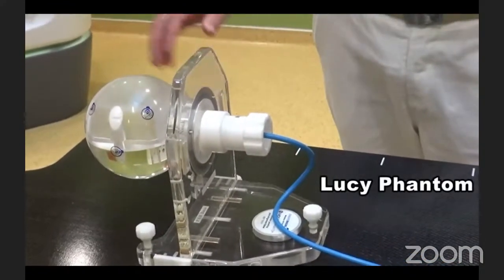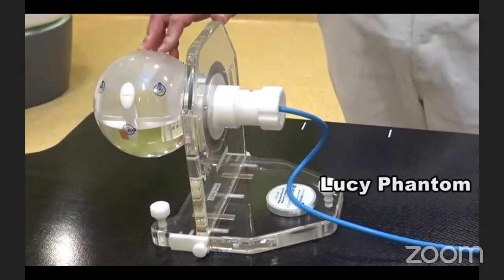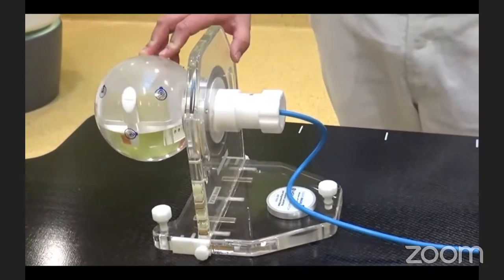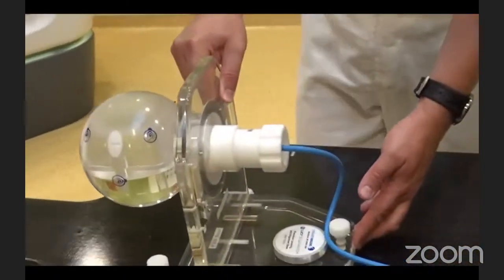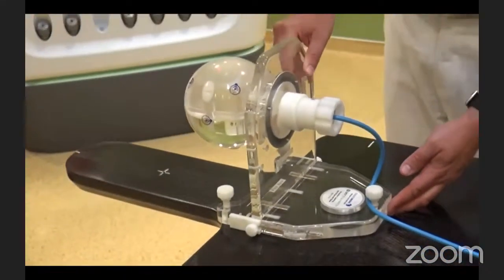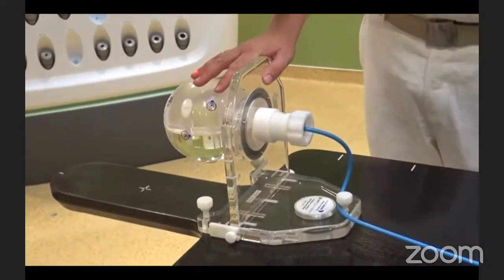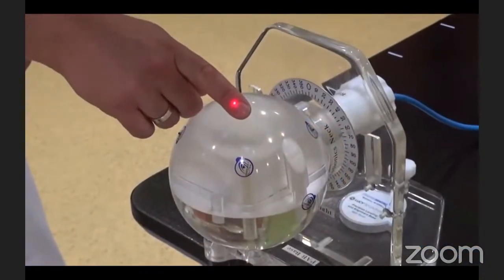The Lucy Phantom is used for patient-specific QA. Before treatment, each treatment plan has to be delivered to this phantom to evaluate the exact point dose value in the middle of the target. So this phantom has an even smaller hole for an even smaller ionization chamber, the so-called pinpoint, and we are positioning this under the accelerator and delivering to this phantom the real treatment of a patient before the first fraction.